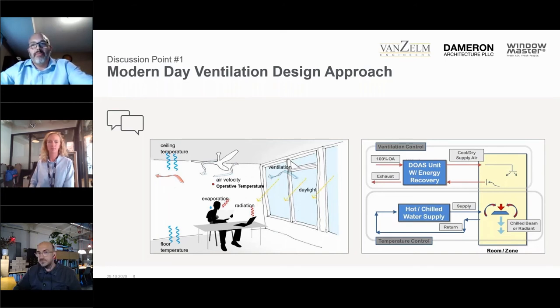But what we've been seeing more and more today is that the ventilation systems going into some of the projects that we've been dealing with are 100% outside air ventilation units. Typically, they're coupled with some form of radiant heating and cooling. That could be a floor, a ceiling, or something to do the temperature control. But the ventilation is done through what we call a DOAS unit, dedicated outside air, with some form of energy recovery, because we're trying to keep it as low energy use as possible.